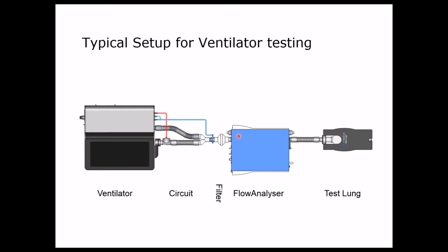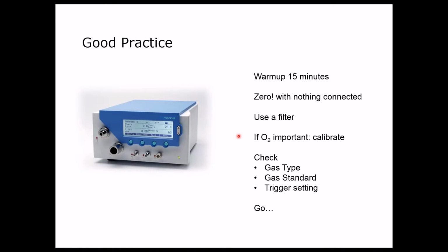Before we start, we have to do a couple of standard steps. We want to warm up the PF300 for 15 minutes. Also, ventilators should be warmed up for some period of time before you do any calibration or any verification procedure. Then, and this is necessary before every measurement, we have to zero the PF300 to make sure there are no offsets in any of the sensors. While you do the zero, no tubes should be connected, because otherwise you risk having some pressure applied somewhere, which then will be zeroed away. Also, we should always use a filter here at the inlet to avoid any clogging with dust.